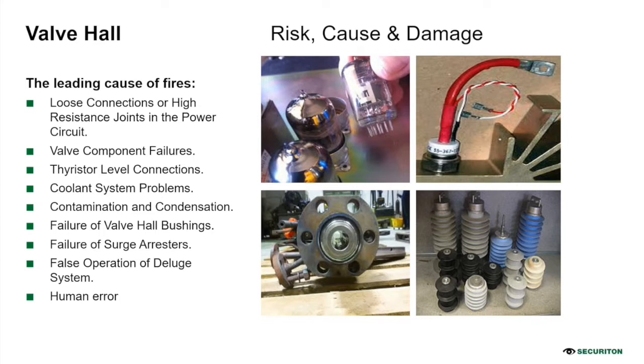Then we have contamination and condensation. Contamination and condensation always occur in this kind of environment. During installation or during operation, this contamination can be caused by heat exchangers, and the leakage of the heat exchangers can basically cause fire in the valve hall.